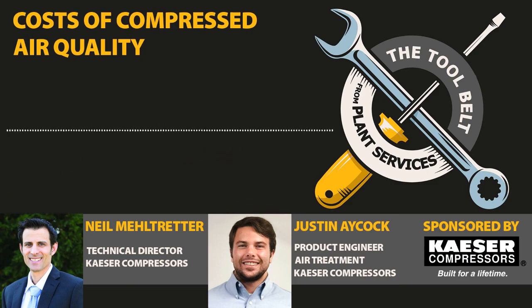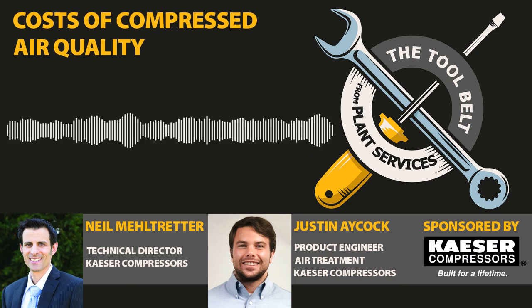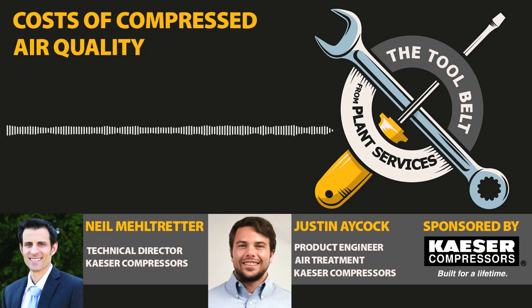But I think first we need to define what the ISO classes are for. The classes are for classifying filtration and drying methods with respect to the big three contaminants for compressed air: particulates, water, and oil. It can be very difficult to replicate or meet these ISO classes in the field because drying and filtration equipment are tested to a standard, ISO 7183 for dryers and ISO 12500 for filters. And the standard test conditions will not be the same as the conditions in the field. So the challenge the air treatment equipment can see is very different for every installation.